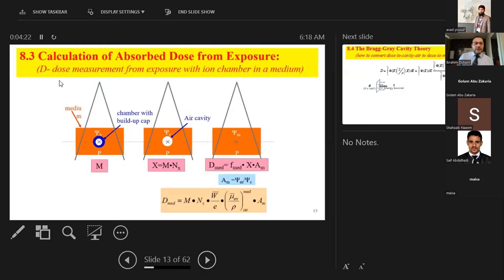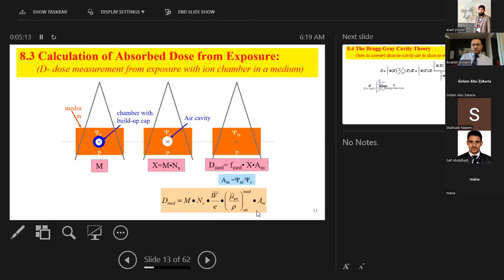If the ion chamber is placed in the medium, the measured value (with build-up cap) is again multiplied by Nx to get exposure. The dose in the medium equals F-medium — the roentgen-to-gray conversion factor — multiplied by the exposure, times the ratio of photon energy fluence from the medium to the cavity air. This gives the full dose to the medium from measurements made within the medium.